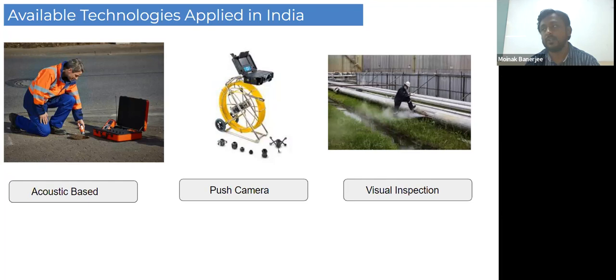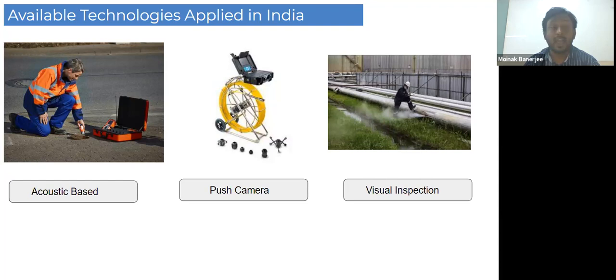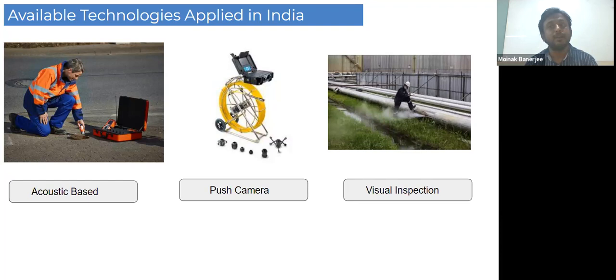The first technology is acoustic-based — using acoustic loggers to detect leakages non-destructively. But in India, population density is very high — it is the world's most populous country. Acoustic methods require a very peaceful environment, generally done at night when environmental noise is minimal. In India's dense urban areas, there have been many false alarms, leading to many wrong random digs in pipelines to fix suspected leaks, causing extra economic losses.